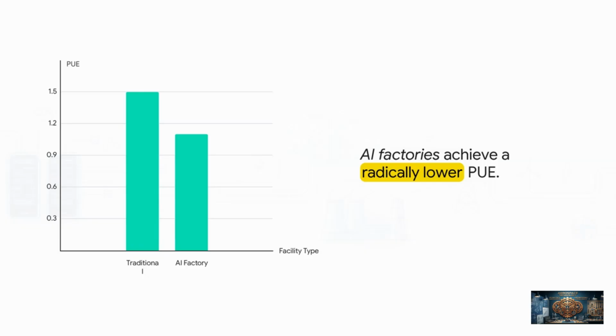How? The chips are so incredibly hot that the liquid cooling them comes back at a scalding 149 degrees Fahrenheit. Because that water is so hot, it can be cooled down just by circulating it outside in the ambient air. No energy-hogging refrigeration required whatsoever.